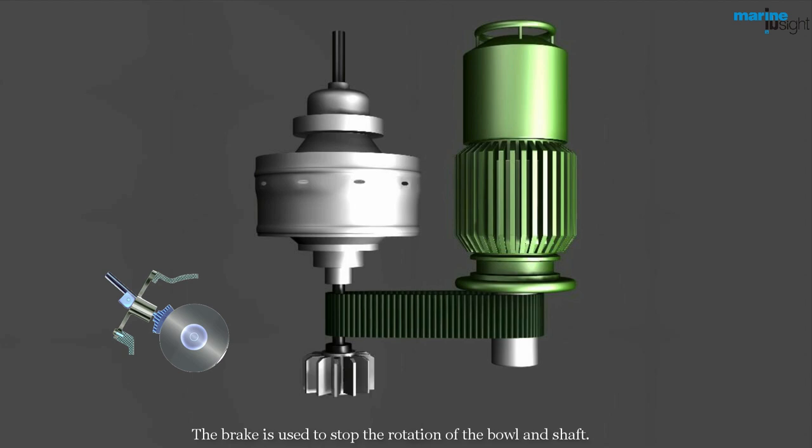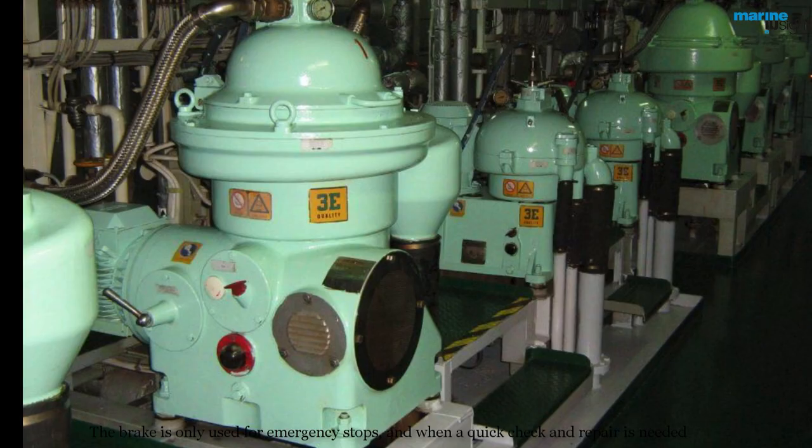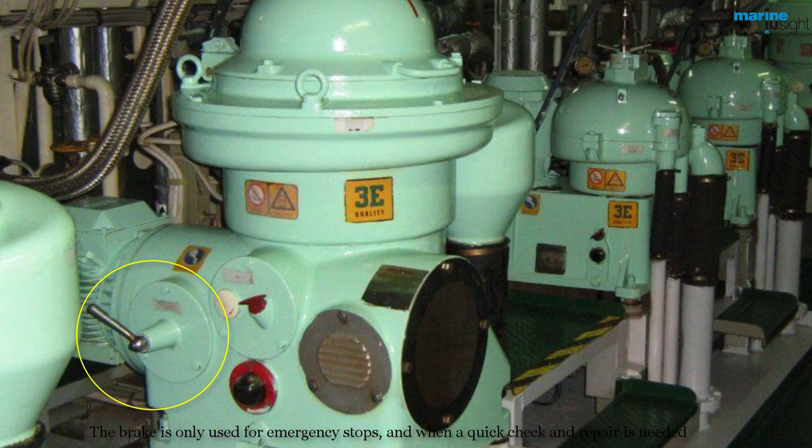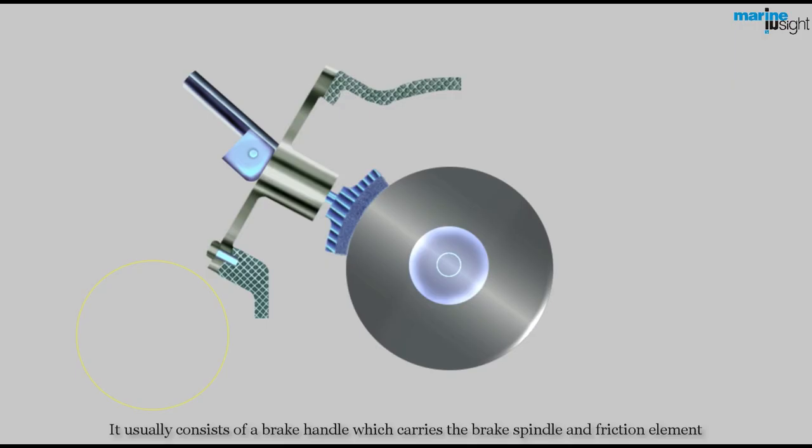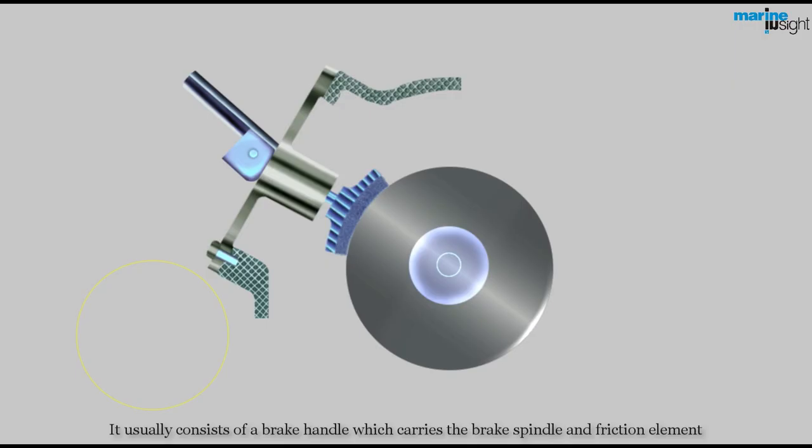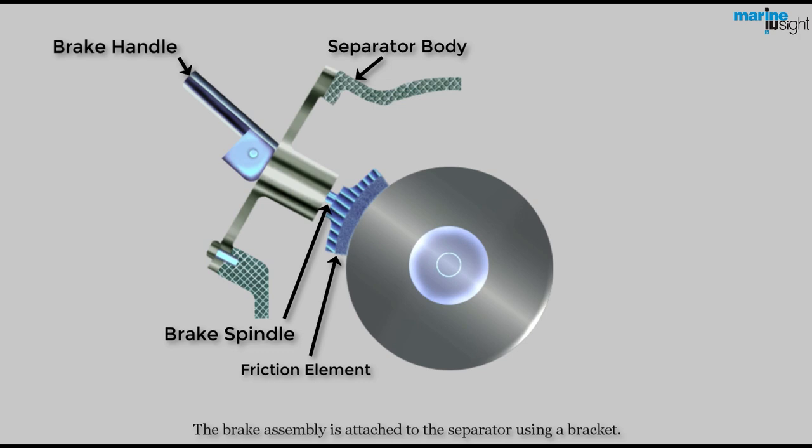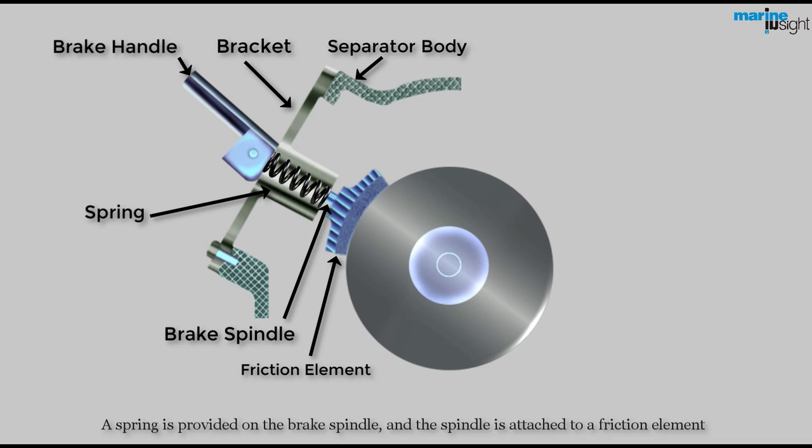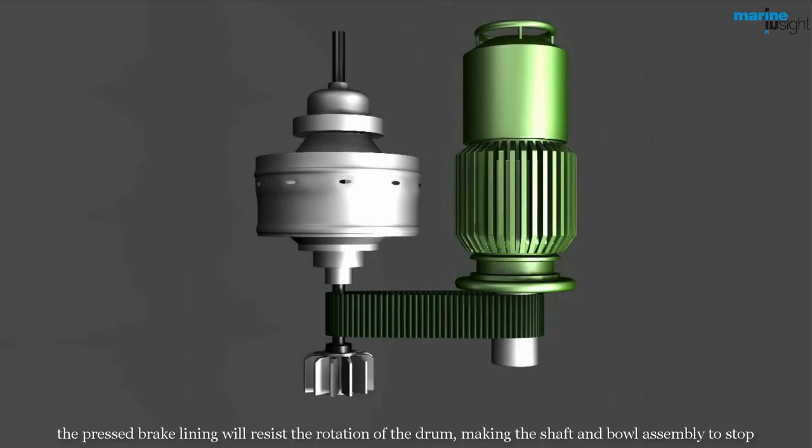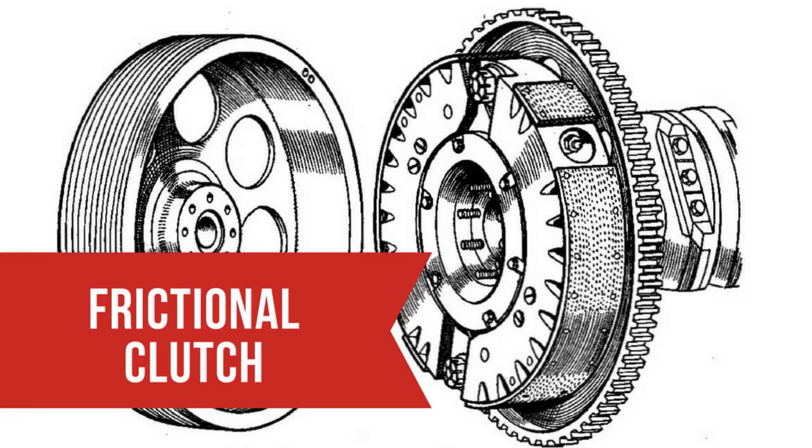The brake is used to stop the rotation of the bowl and shaft. The brake is only used for emergency stops and when a quick check or repair is done. It usually consists of a brake handle, which carries the brake spindle and friction element. The brake assembly is attached to the separator using a bracket. A spring is provided on the brake spindle and the spindle is attached to a friction element. When the lever is lifted, the spring which was kept compressed releases and the brake lining is pressed against the outer surface of the frictional drum. The pressed brake lining will resist the rotation of the drum, making the shaft and bowl assembly to stop.